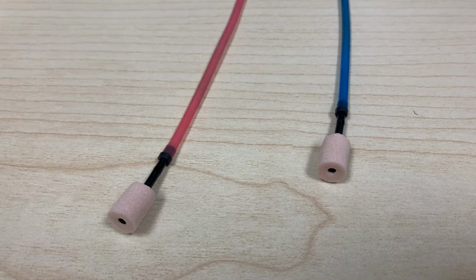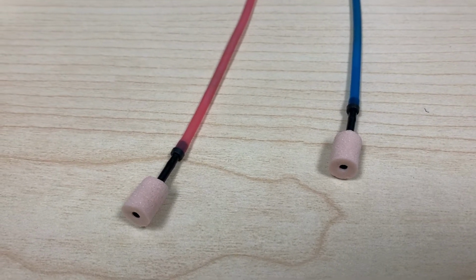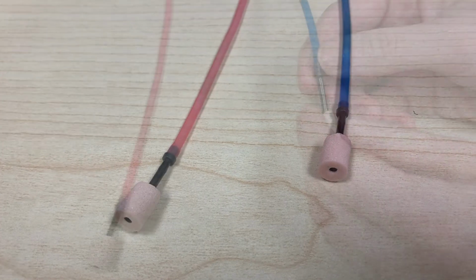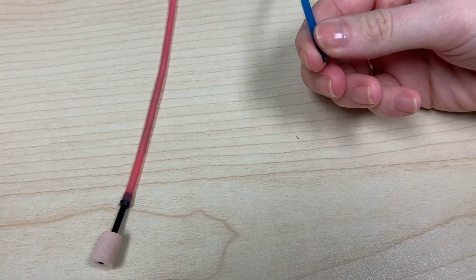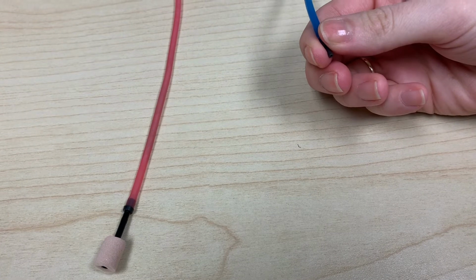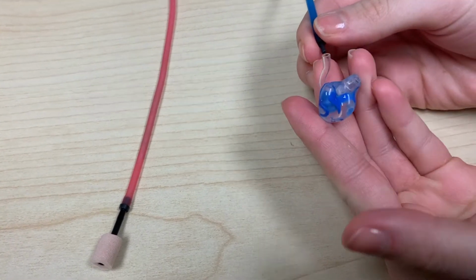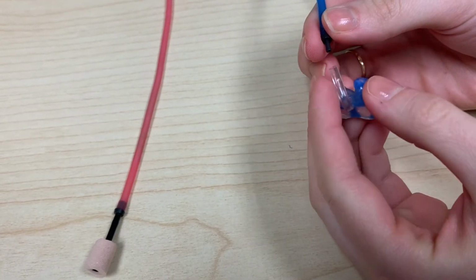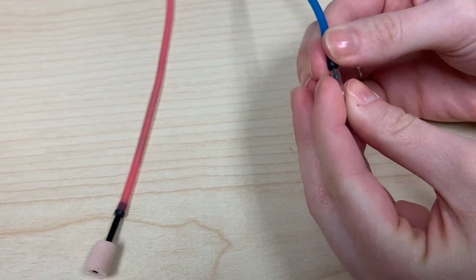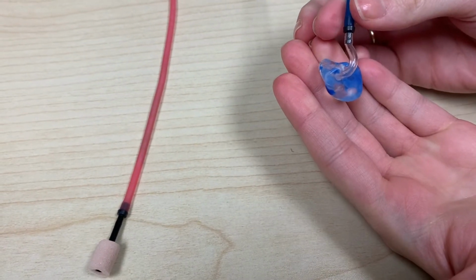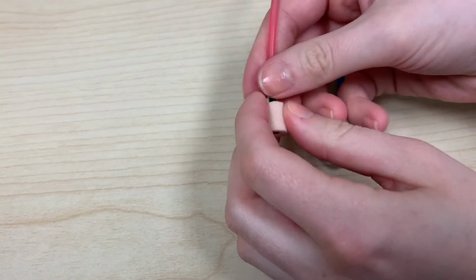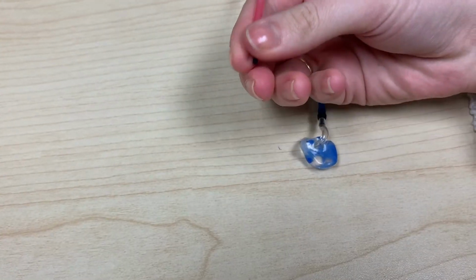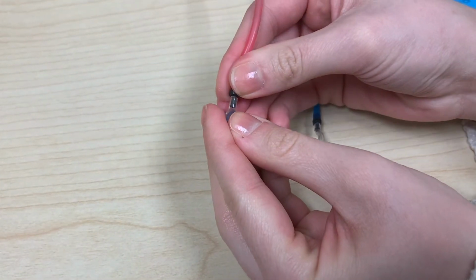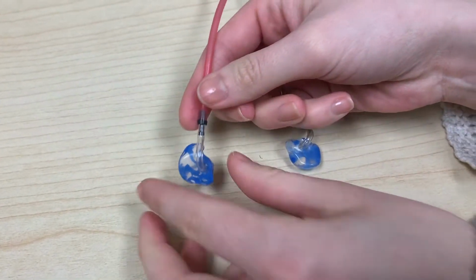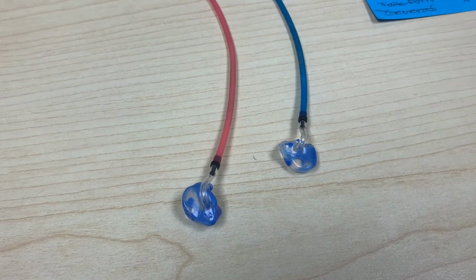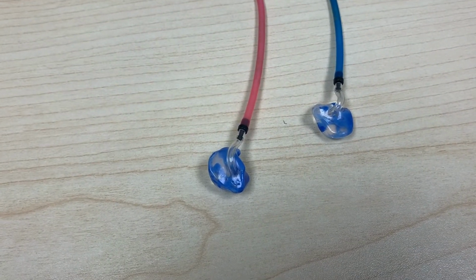But if they have their own personal molds and those molds are not vented, you can actually place them on this. So you would just remove the insert, or hopefully there's not one on there. You don't want dirty inserts on there. You find the corresponding left mold for the left side and insert it in the nubbin. And then you would do the same for the right side. And your audiometer should still say insert phone, but now we're using the custom molds, which will help when programming hearing aids.